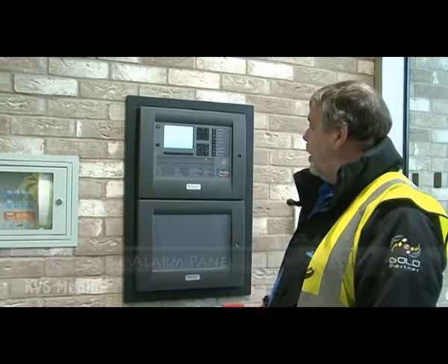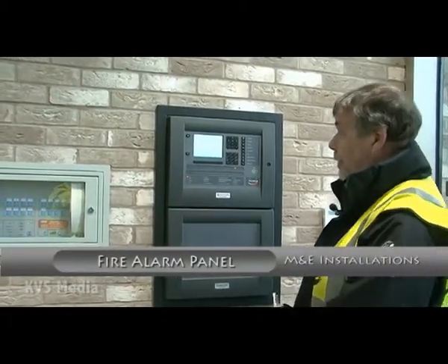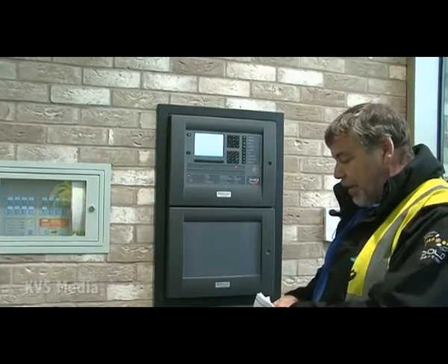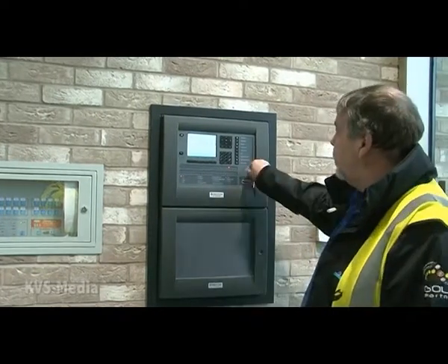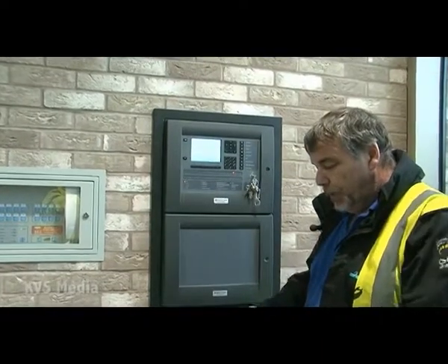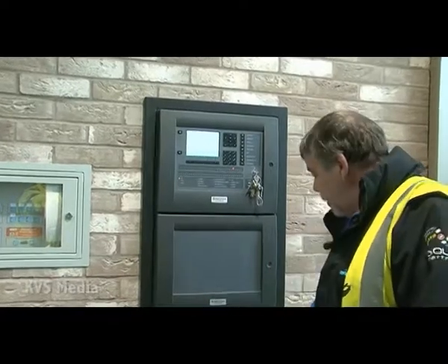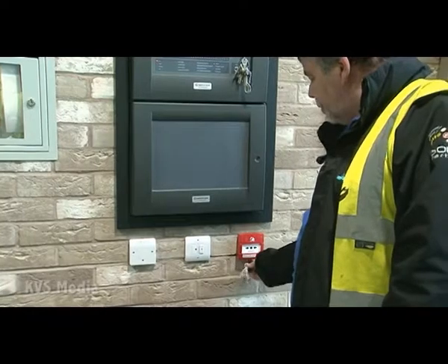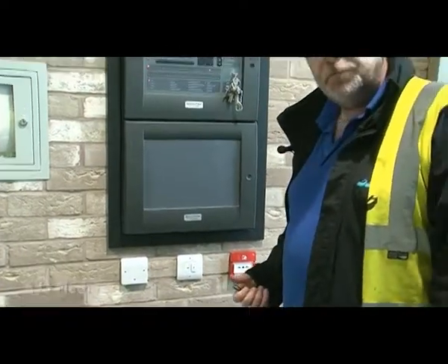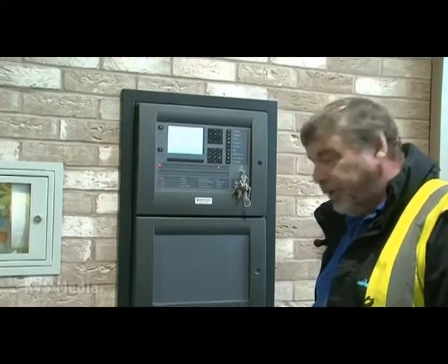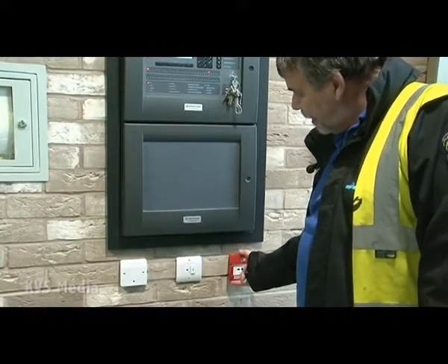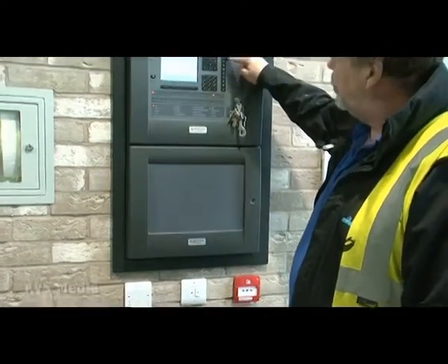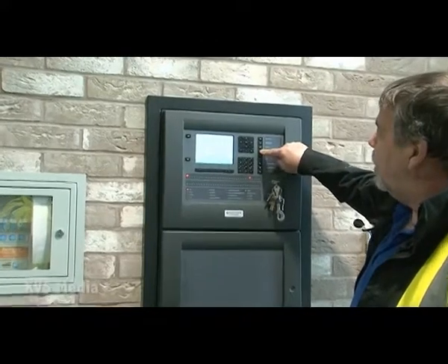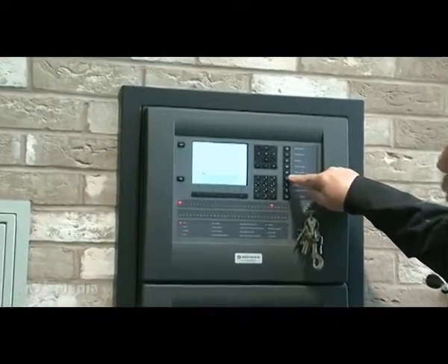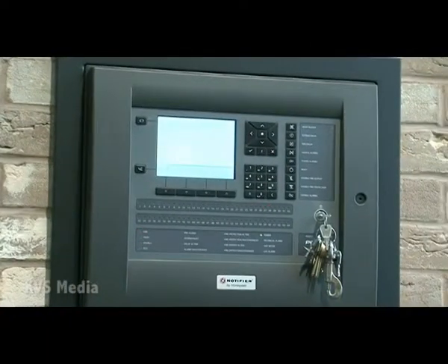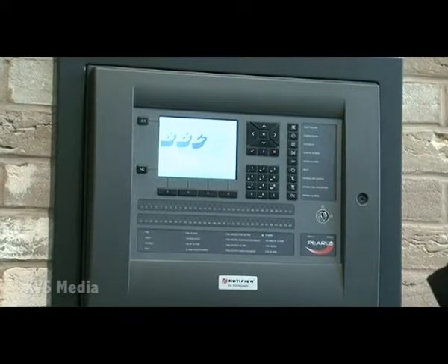So what we're going to do is, with the system in normal mode, which unfortunately it isn't at the moment, I'm going to put a controls activate key in the panel to enable the push buttons and turn that to the right. And for a weekly test you utilise this shape key, insert to the middle of the break glass at the bottom until it clicks, and then pull the key out, generating a fire condition. And having got the fire condition to register, you then snap the break glass shut again by squeezing it top and bottom. And then on the panel we can mute the internal buzzer, silence the alarms, and ultimately we can then press the reset button, which should take us back to a system normal, and remove the key. And that is basically how you go about a weekly test.